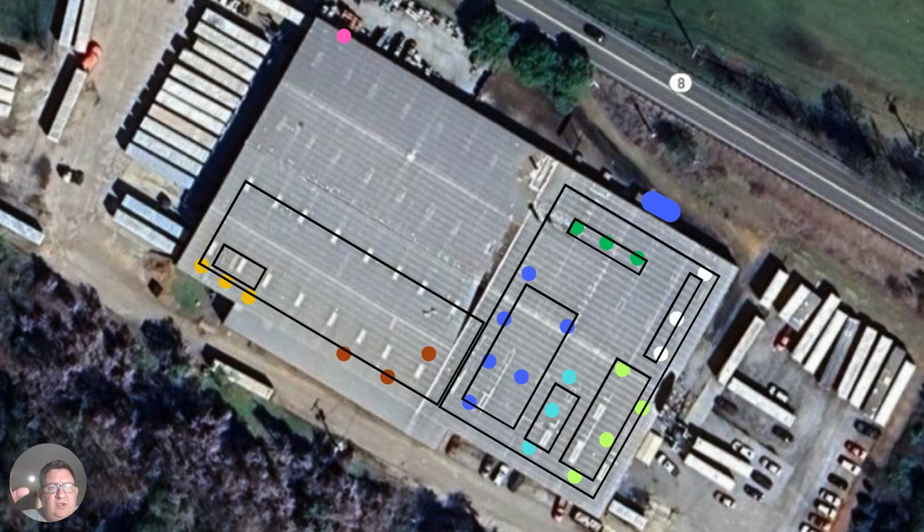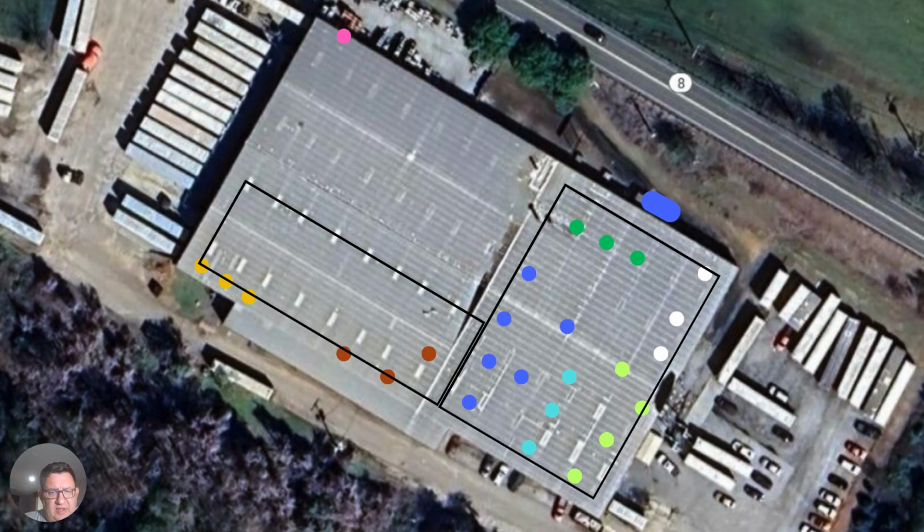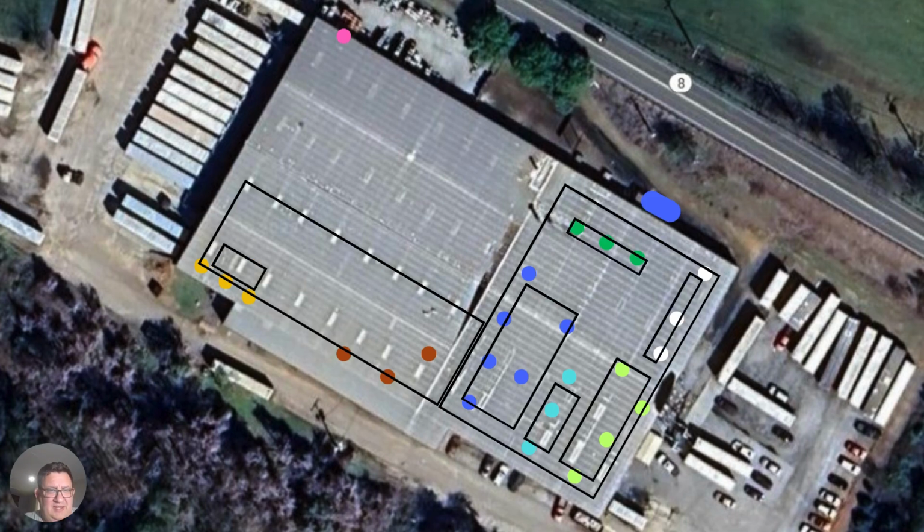Now, let's go back to this receiver tank, right? In fact, we'll go back all the way. In this case and the other cases with the straight header, with the loops, and even with the loop and ladders, the demand profile is going to change all the way the length of its range, right? And your primary storage and your distribution piping are sized to account for all of that. But when we use this design, we can look at the cycle and the individual characteristics of that process group.